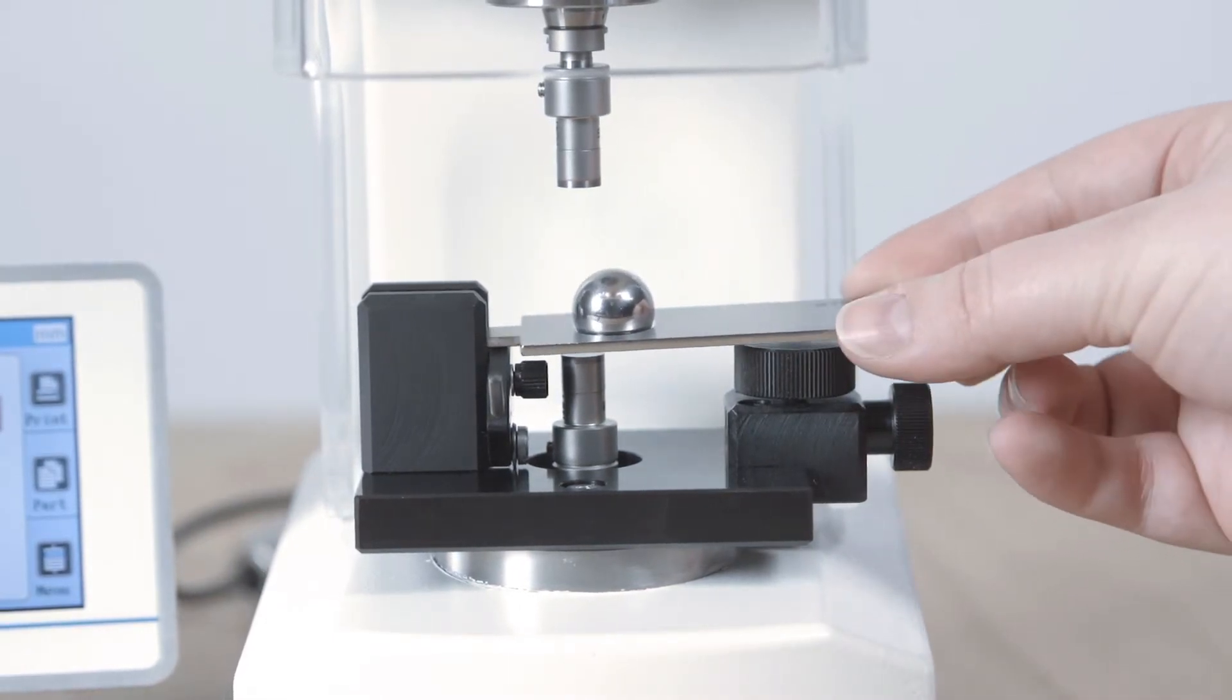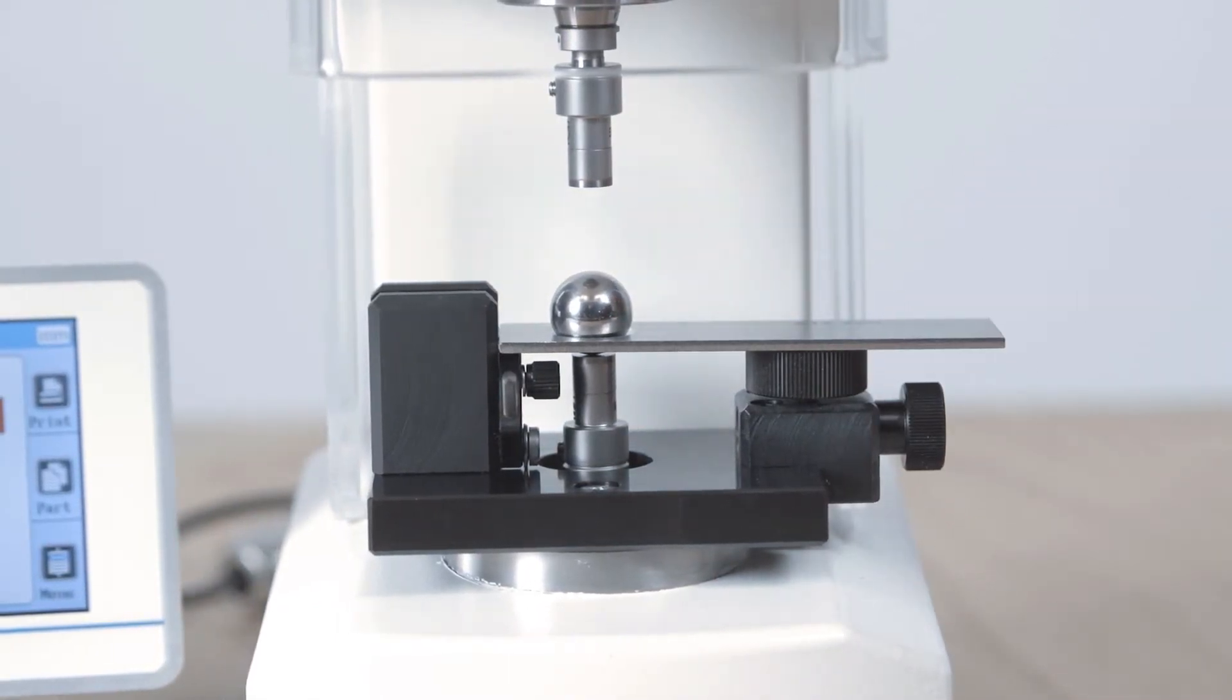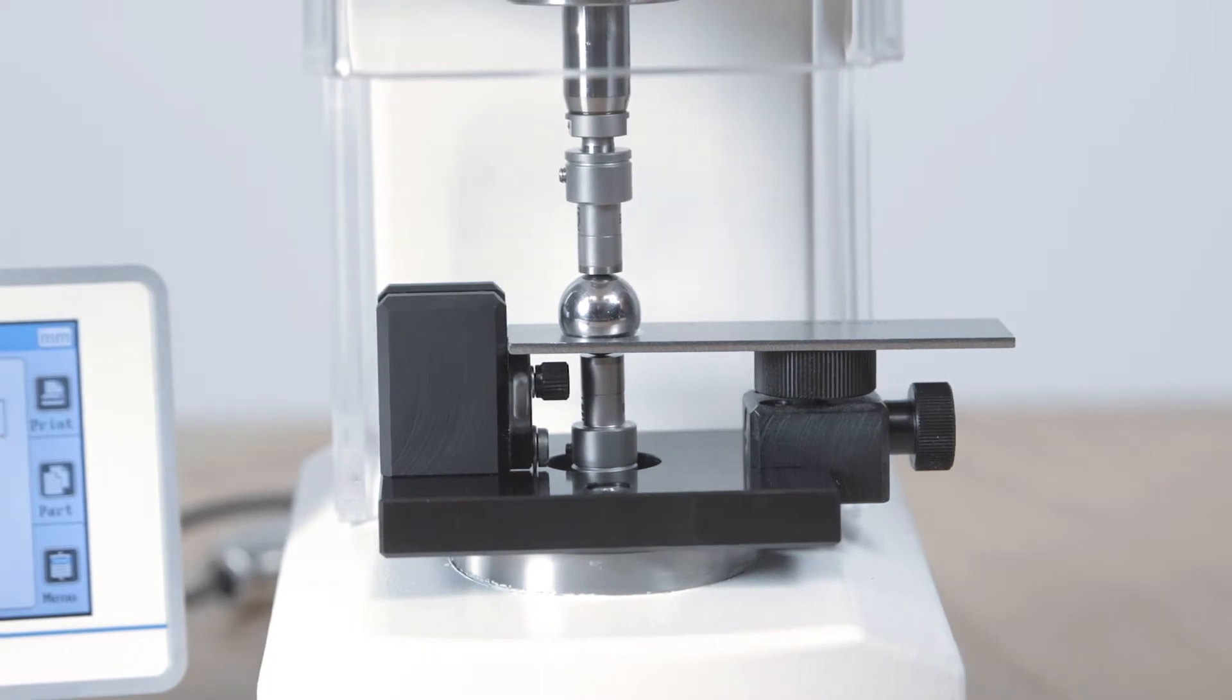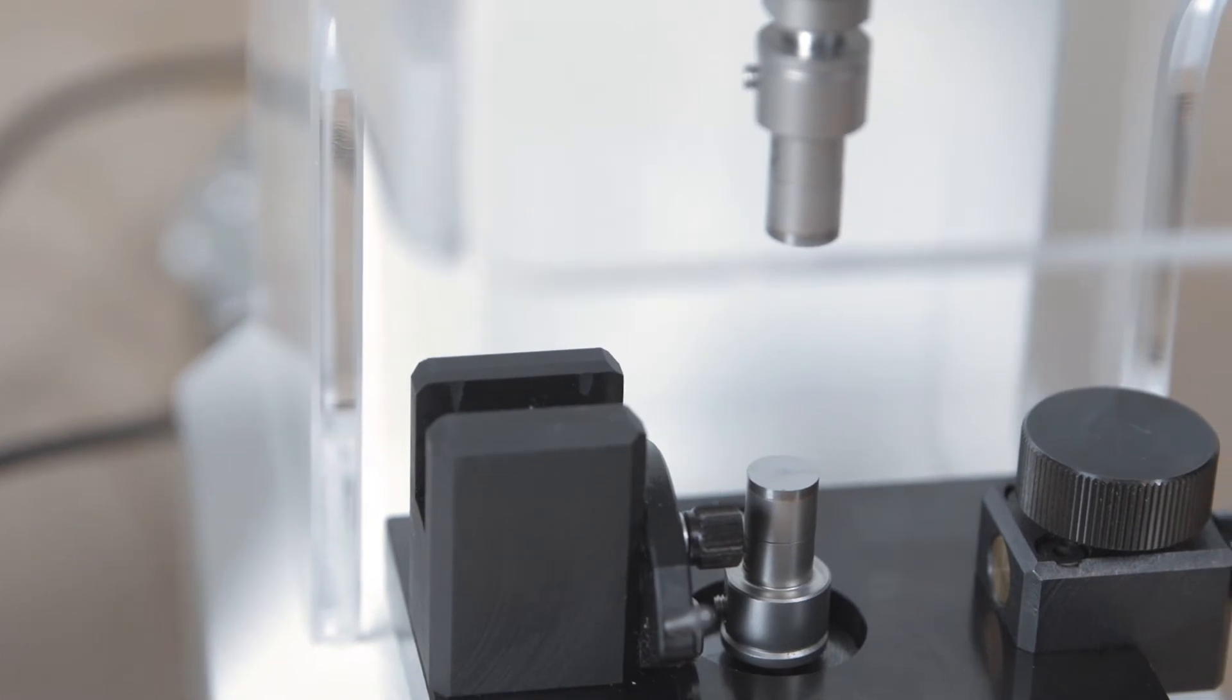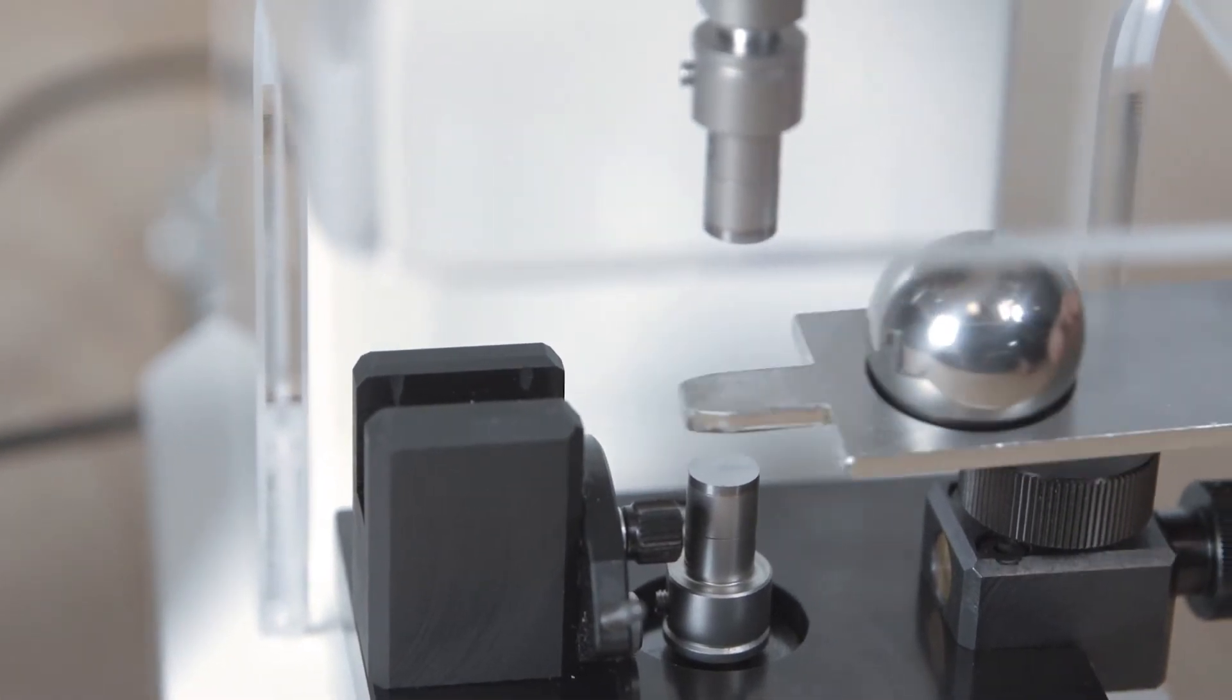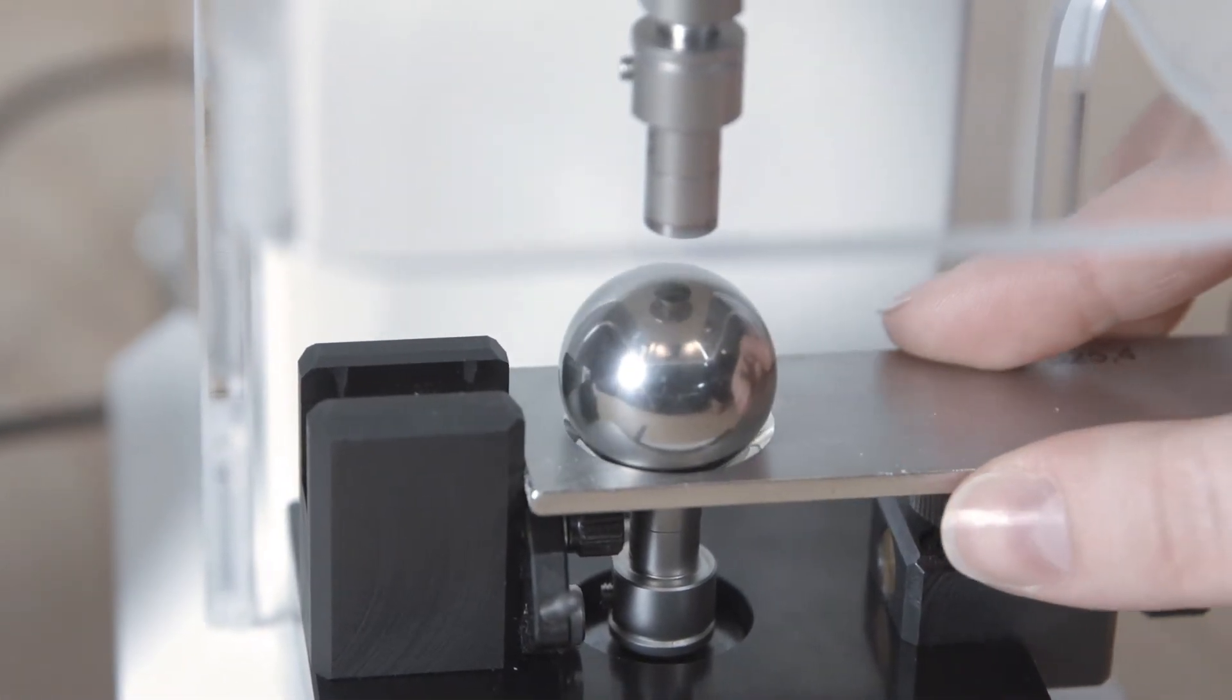FeinMess Suhl has developed a special height adjustable table to calibrate balls. With the help of holding plates that have been adjusted to the size of the balls, the various balls are positioned safely between the measuring surfaces with no thermal influences.